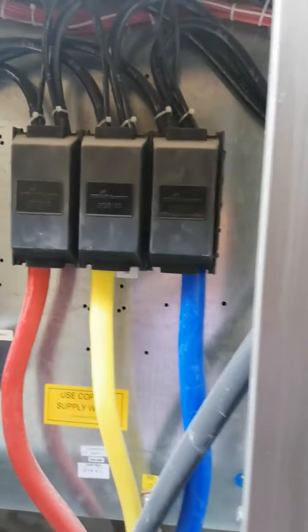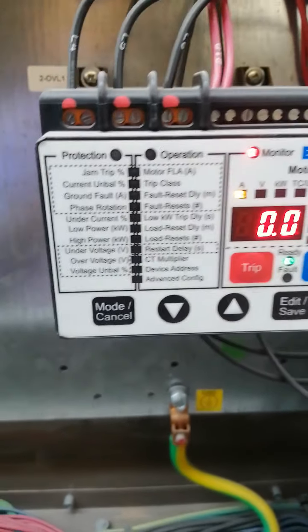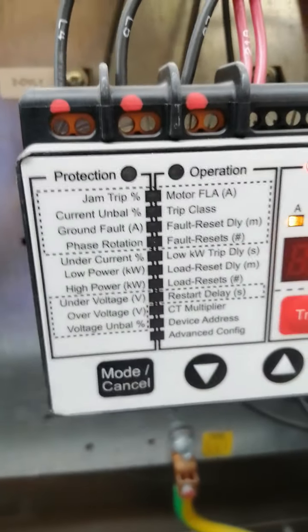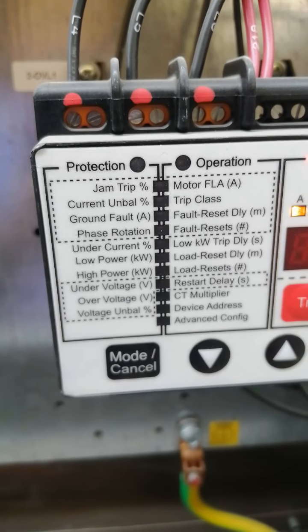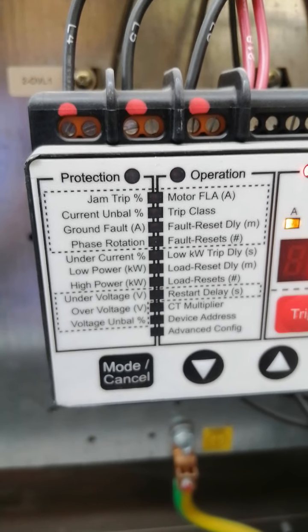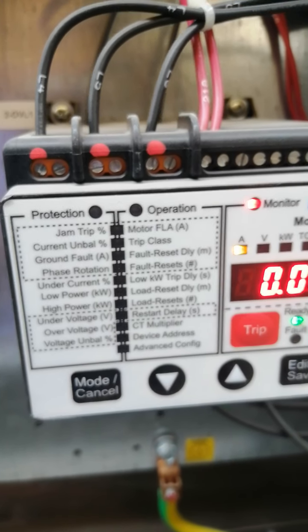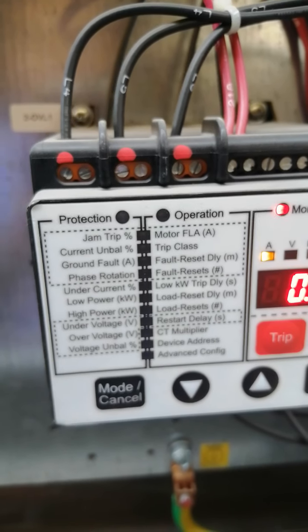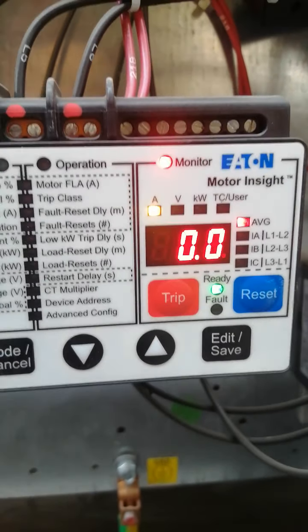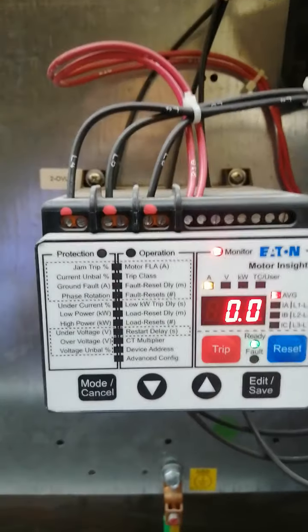Now I will show you the starter and motor protector inside the power circuit. Okay, so guys, this is our incoming from main supply RYB, and after that it goes to system 1 contactor, and that is system 2 contactor. There you see 3 CT going to our motor protector. Check what protection this motor protector has: jam, trip, motor full load ampere, current unbalance, ground fault, phase rotation, under current, low power, high power, under voltage, over voltage, voltage unbalance. Okay, so that is Eaton company manufactured motor protector.